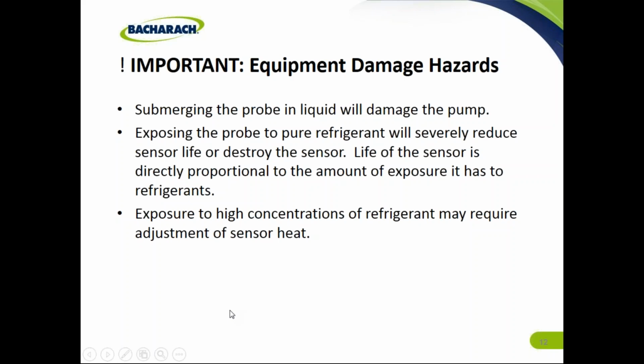Submerging the probe in liquid will damage the pump, as it will pump up that liquid. Exposing the probe to pure refrigerant will severely reduce the sensor life or destroy the sensor. Life of the sensor is directly proportional to the amount of exposure it has to refrigerants. Exposure to high concentrations of refrigerant may require adjustment of the sensor heat.